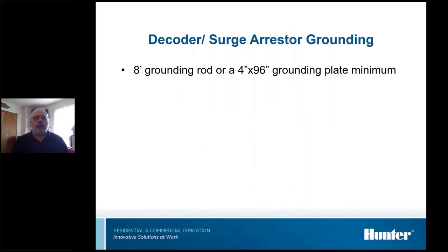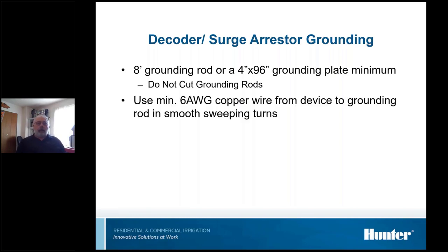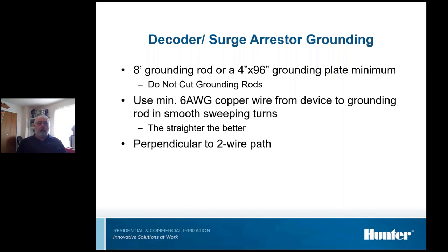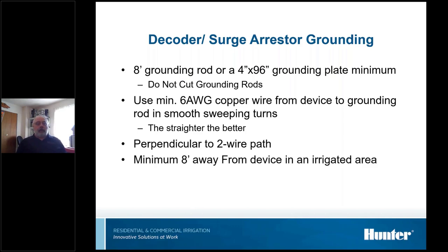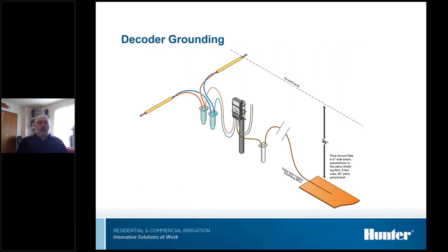As far as for decoders and surge arresters, it's really pretty much the same thing. We're either going to use a rod or a plate. Don't cut rods off. We're going to use 6-gauge wire to attach the two together. The straighter the better, perpendicular to the wire path. Like I say, it's almost the same thing. So here's what it looks like when you ground a decoder. This is one of our ICD decoders with the internal grounding. It's perpendicular to the wire path, and in this case, they used a ground plate 36 inches deep.